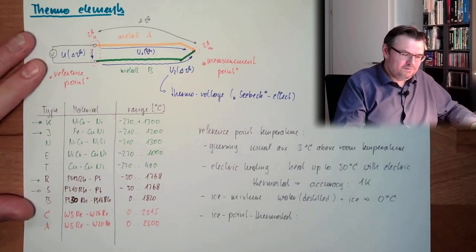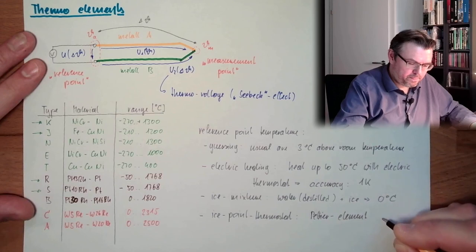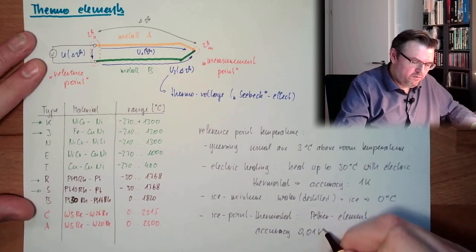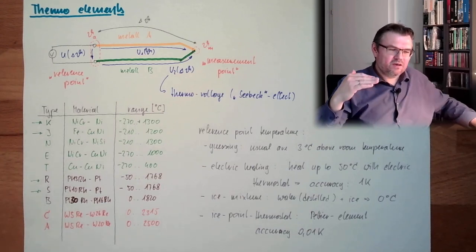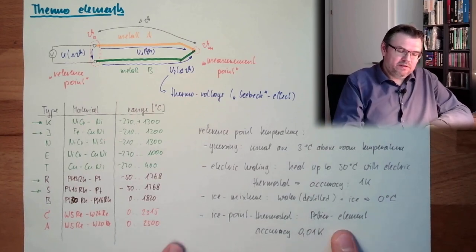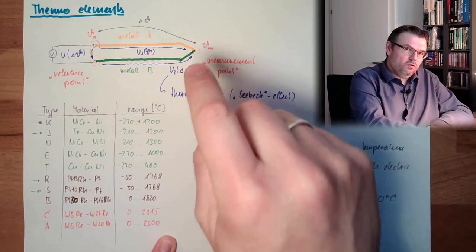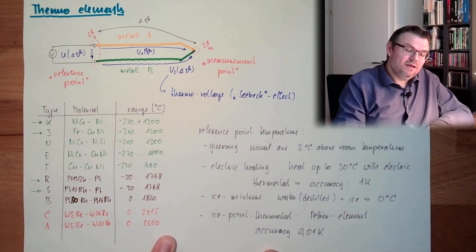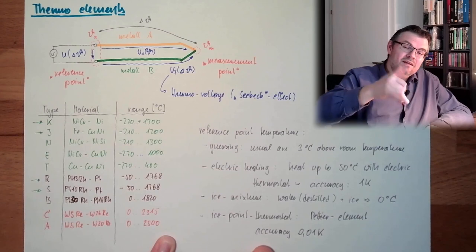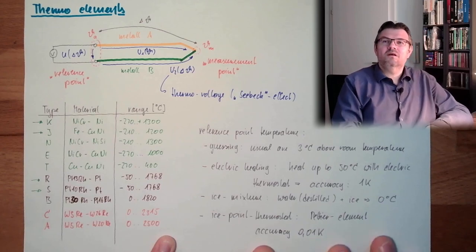These are working with a Peltier element and have an accuracy of 0.01 K. So it's held electrically controlled with a Peltier element which can heat and cool. By the way, a Peltier element is nothing else than a thermo element. However, we are not measuring the voltage, we are applying the voltage. If we apply a voltage in either direction, this will get hot or cold. So it's the same effect but the other way around. Here we are measuring the thermo voltage, and here we are applying a voltage which will result in a temperature gradient.